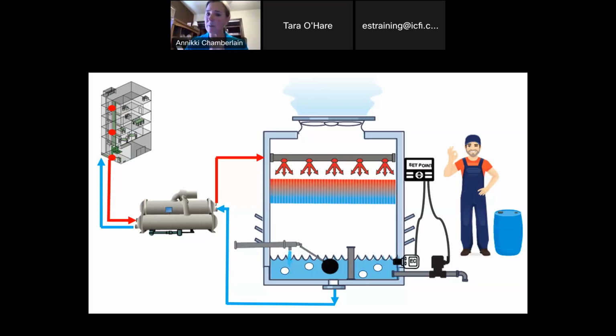Oftentimes it's conductivity that we're running the towers off of because it's something that's very easy to measure, and we'll talk about that a little bit more in a second. We could have an issue with the chemical feed, too much, too little. Maybe running out is more of a mechanical issue. We could have a change in water quality coming in. I know places like the Phoenix area switch between surface water and groundwater, and that has a big difference in mineral concentration. So tons of stuff can go wrong on both mechanical and operational.